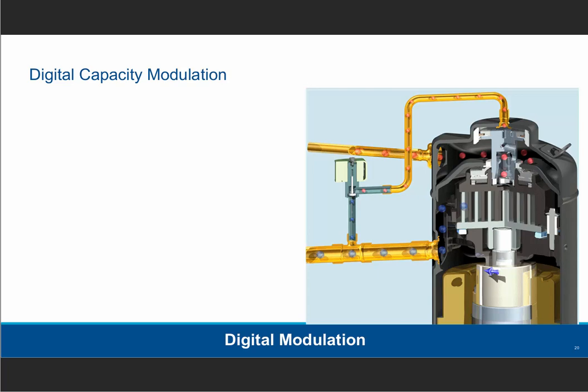Taking a look at digital modulation, if you're not too familiar with digital modulation, this is kind of a cutaway here of a digital scroll compressor. And what's unique about it, it has this little cap on the top, and that cap is there to accommodate a piston inside that particular compressor. And there's also a copper tubing that goes to a pulse width modulated solenoid valve directed to suction.